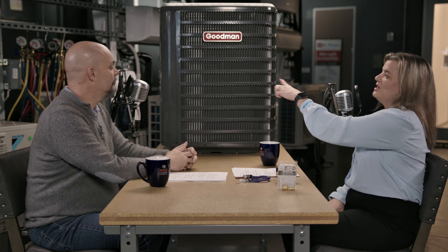This is a high pressure switch. We've always had it on all our heat pumps and on select ACs, but now every AC is going to have this. This is our contactor, which previously was not enclosed — now we've got that enclosed, and that's going to be a benefit as well. You would see that we have red valves, and that will indicate that it's the A2L. This is a reverse thread adapter that will be used for the R32 cylinders — you could use a reverse-threaded hose or we have these adapters. We've had these available for ordering. We thank our ductless team for blazing the way — we've had this worldwide and they were able to launch their Atmosphere product in 2021. We work closely with them and utilize their experience as well.